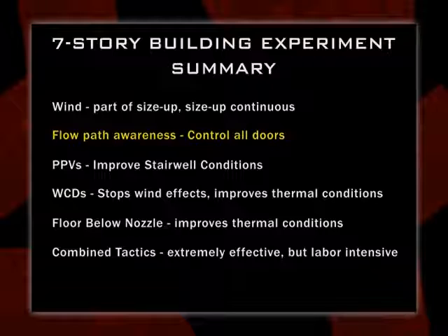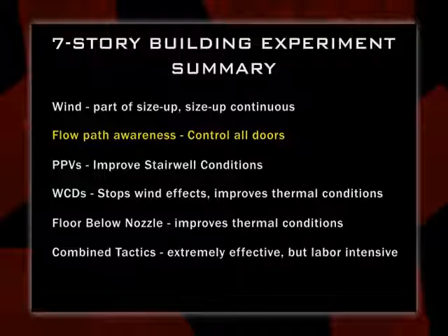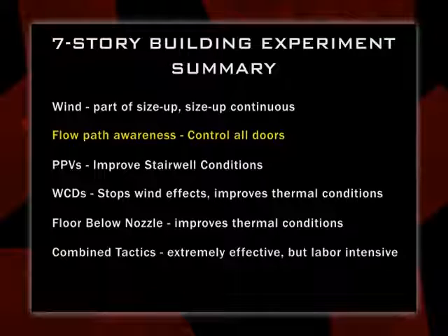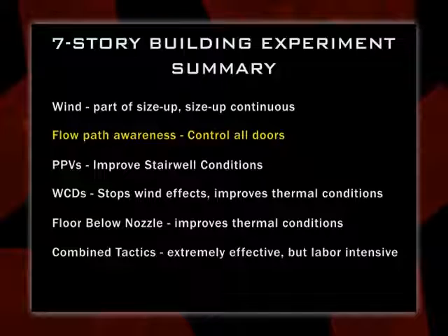One of the biggest conclusions that's going to come out of this is the impact of vertical ventilation in these stair shafts with fires that may be 5 floors remote and on the opposite side of the building of where that stair shaft is opened. You want to get a fire to grow and to flash over, open the bulkhead door, open the stairwell, and allow it to vent vertically. That will allow that fire to progress much quicker than if you left that door shut.